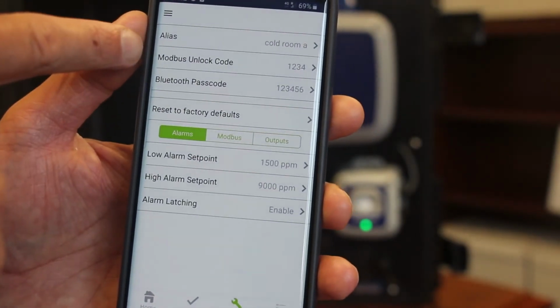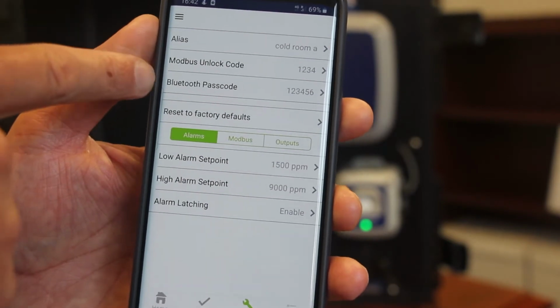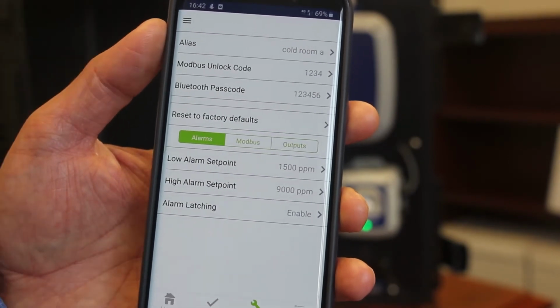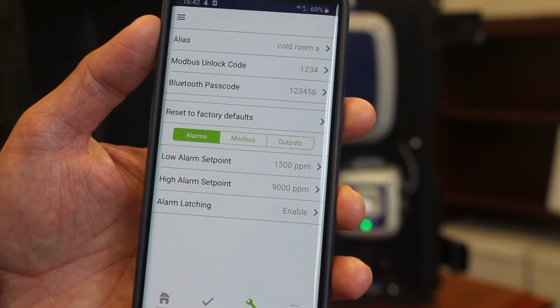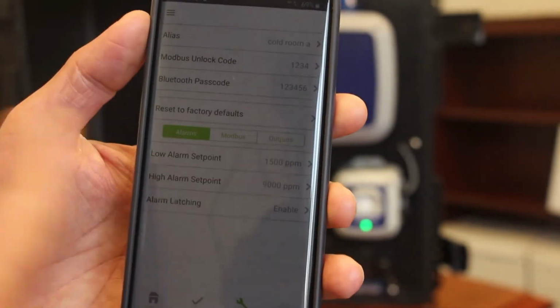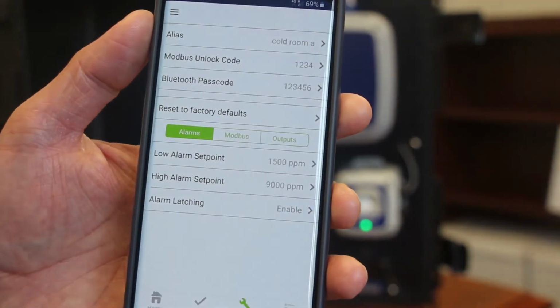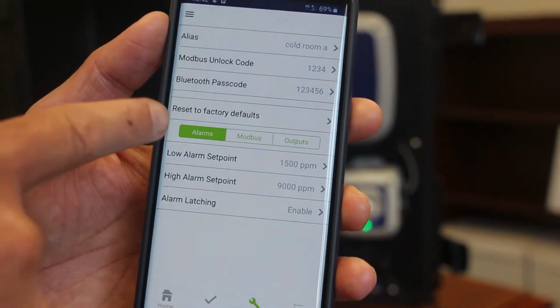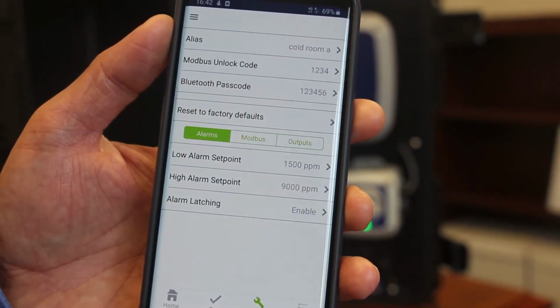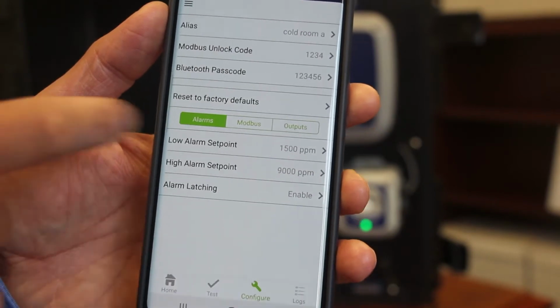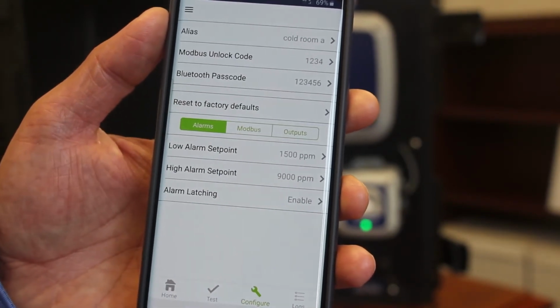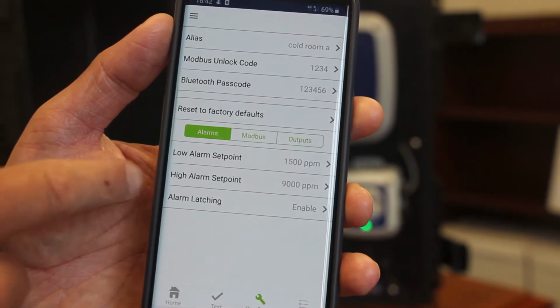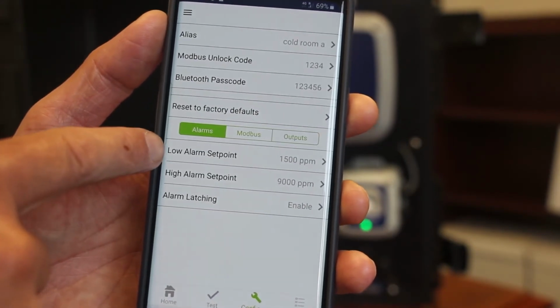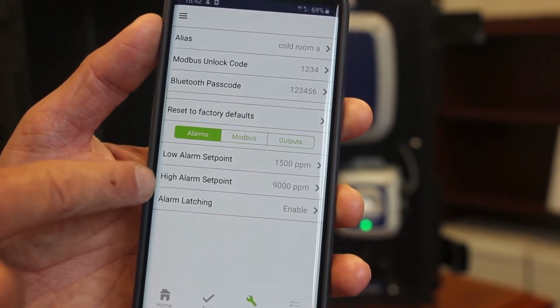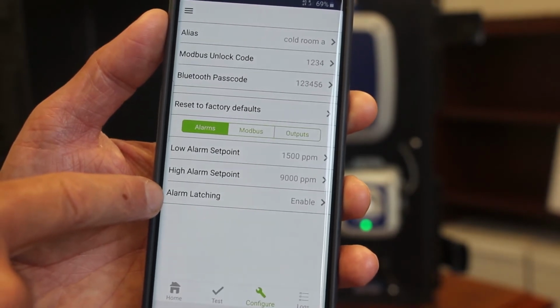You'll notice here that there is some passcodes in place for both the Modbus and the Bluetooth connectivity, and that's again to provide some level of security so that the configuration, for example, can't be tampered with on the instrument. You can also set the instrument back to factory default settings. And then the final section here is around your alarms and your alarm behavior. So you can see here you have low alarm set point, high alarm set point, and you can also set your alarms to be latching or non-latching.